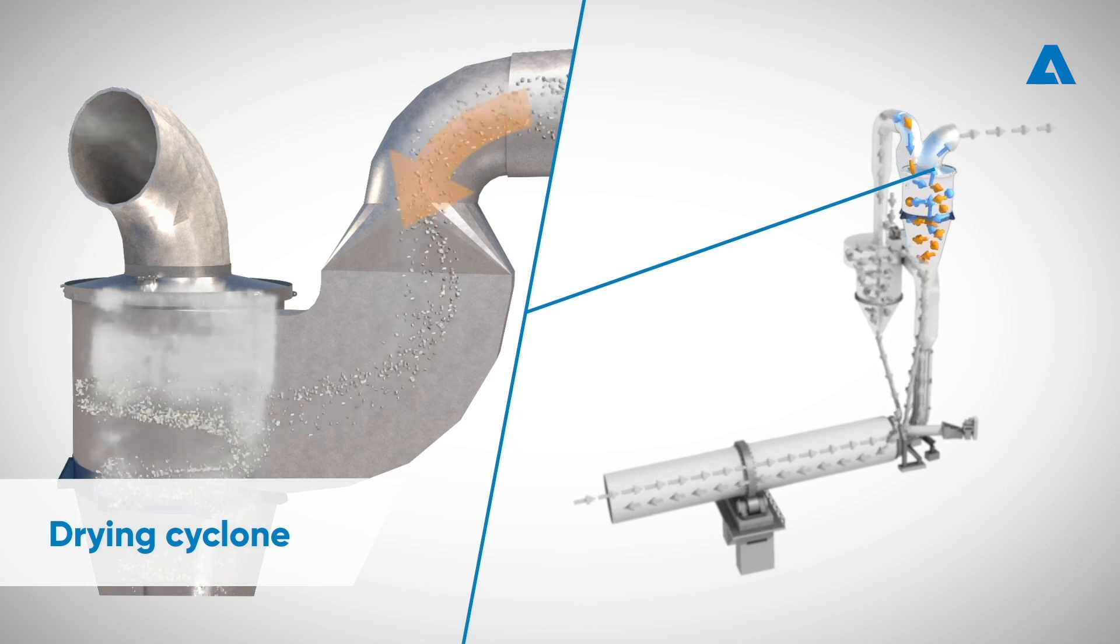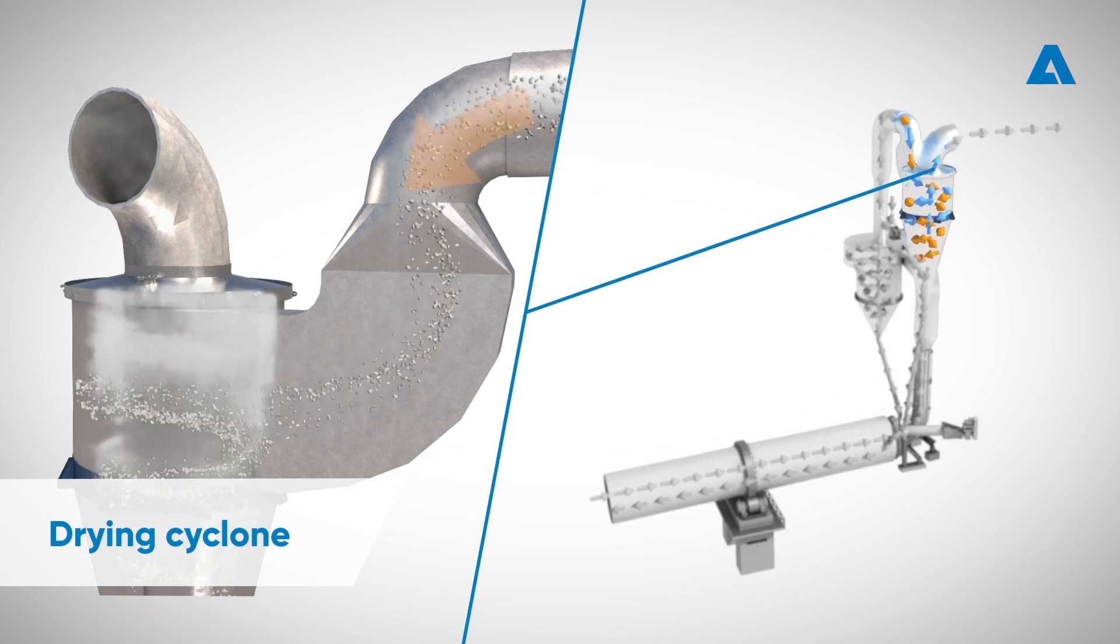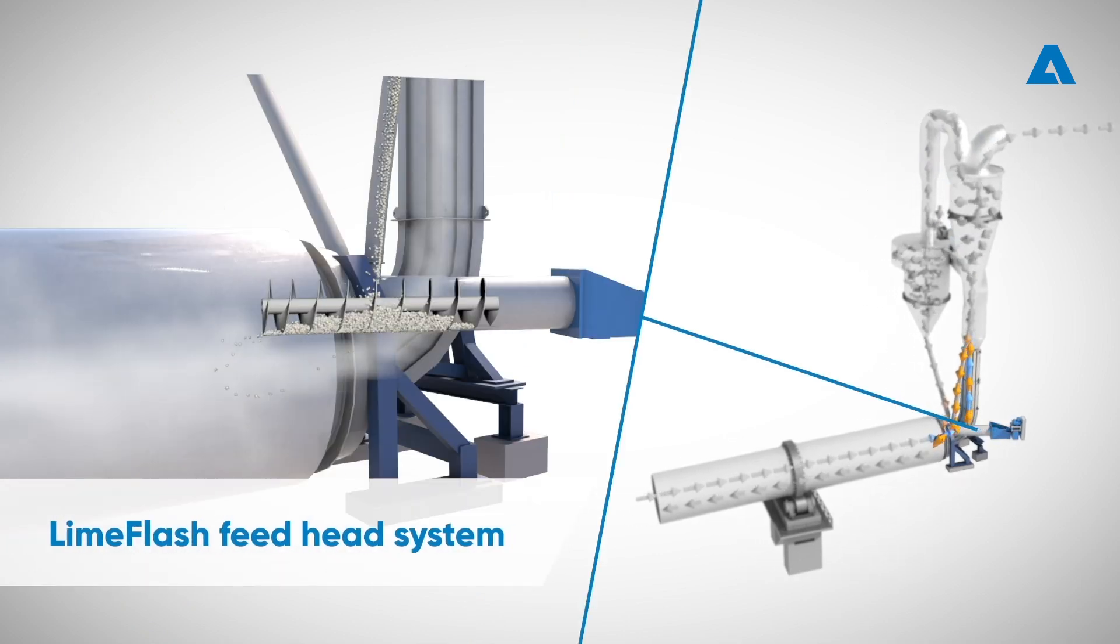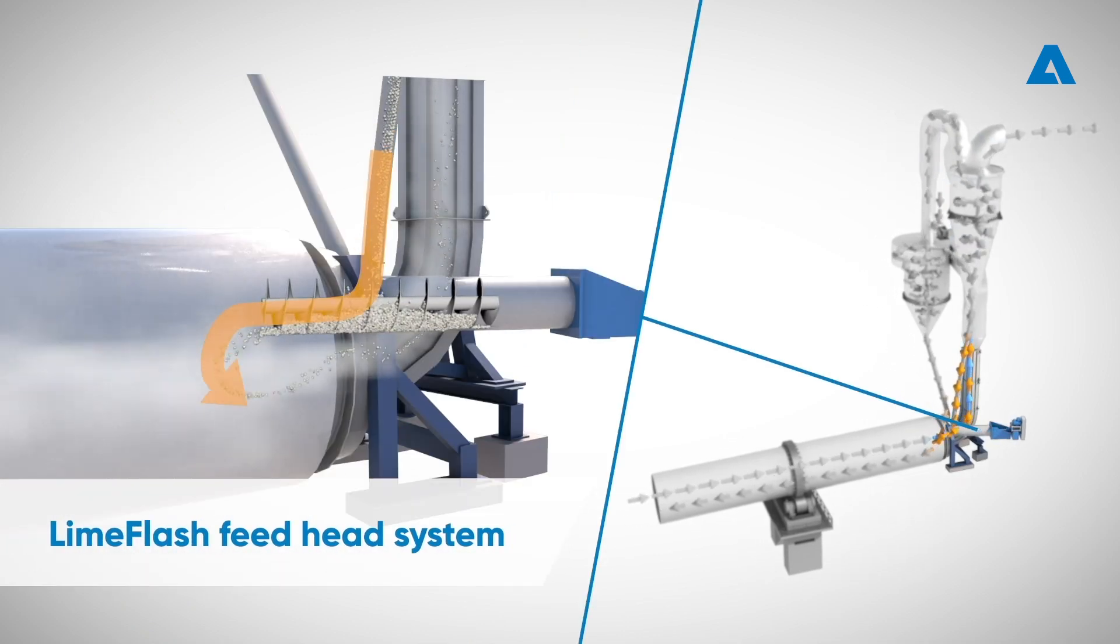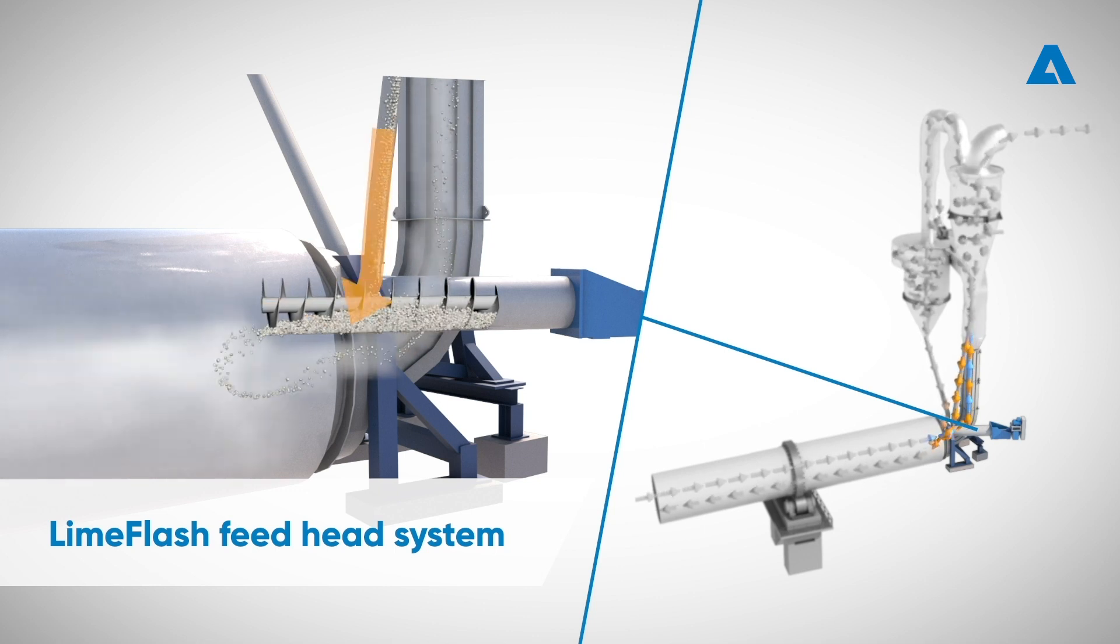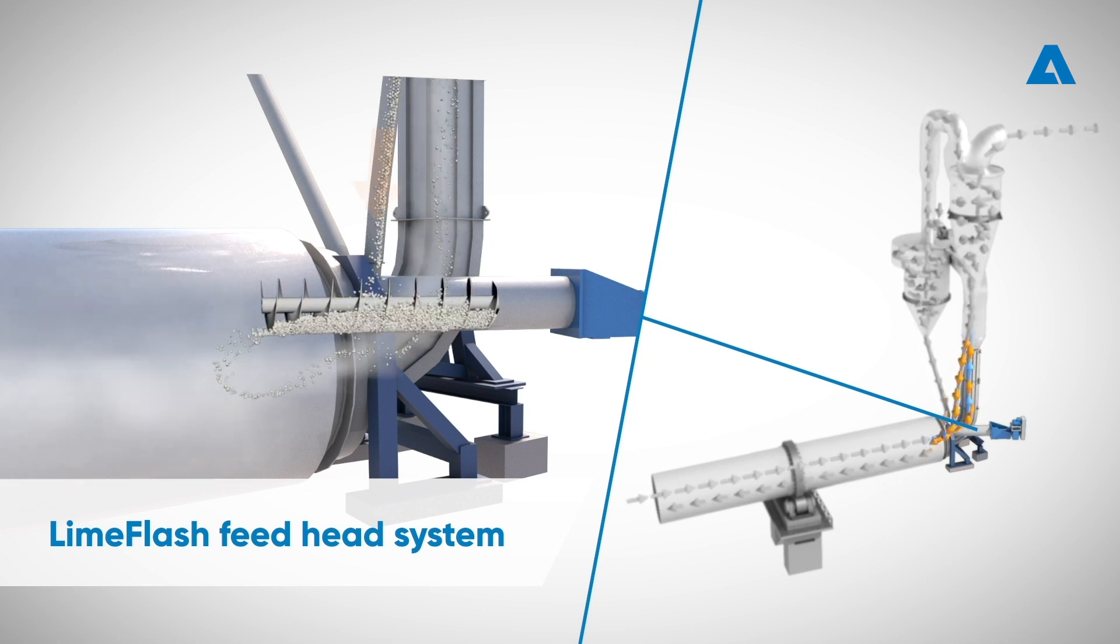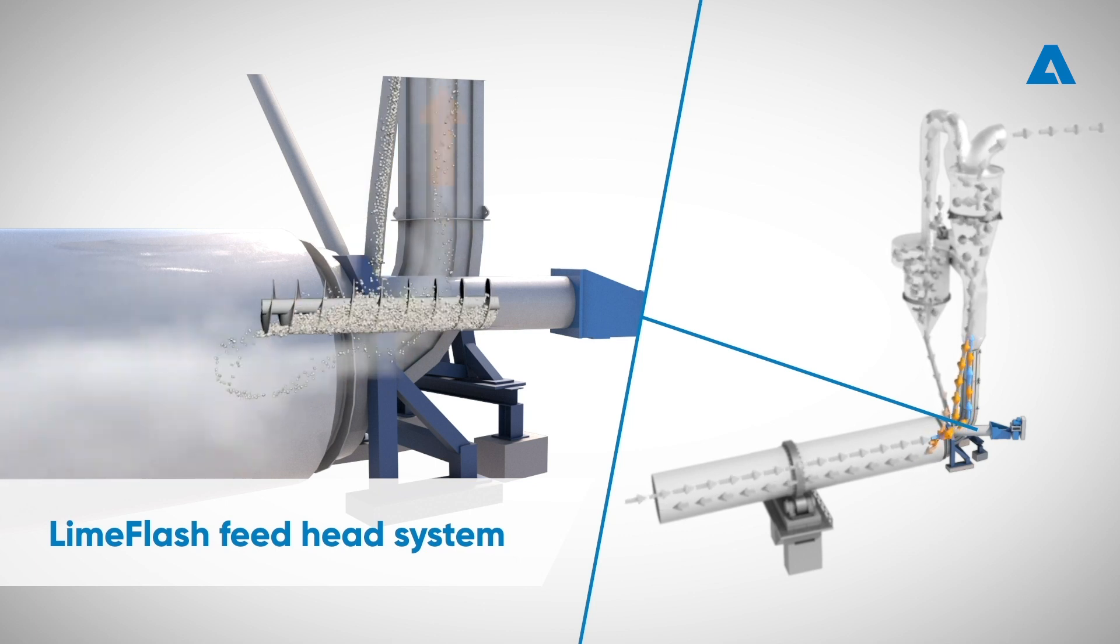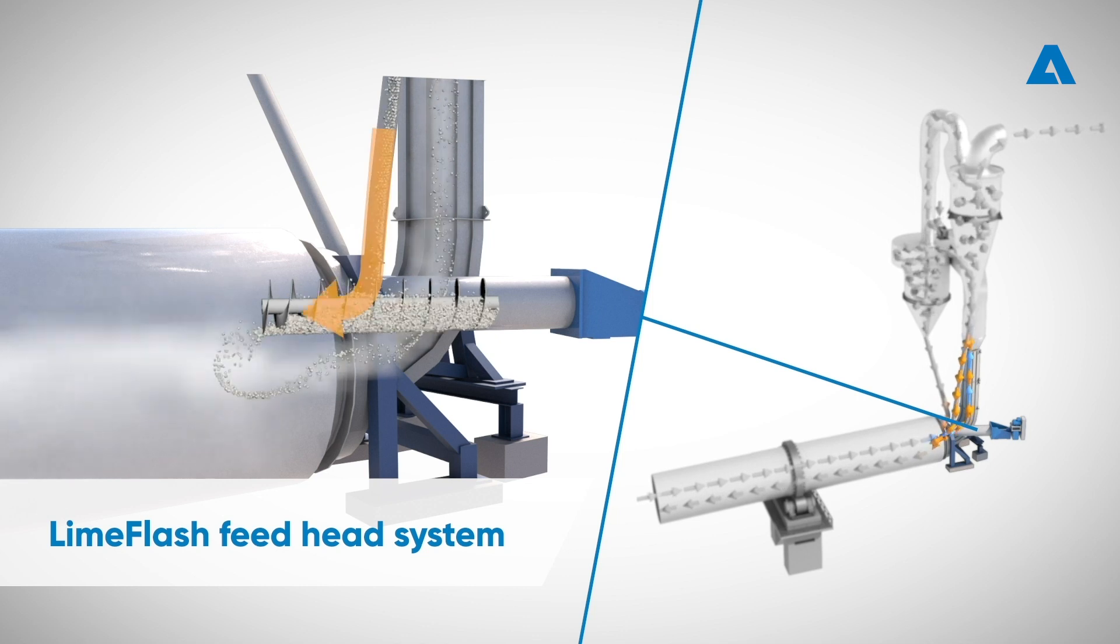The drying cyclone separates the dried lime mud from the flue gas. The lime mud then flows by gravity through a chute into the preheating feed screw, which feeds the dried mud into the flue gas stream again in the LimeFlash H lime kiln feed end. Lime mud is now further heated to about 500 to 600 degrees Celsius and carried with the flue gas to the preheating cyclone.